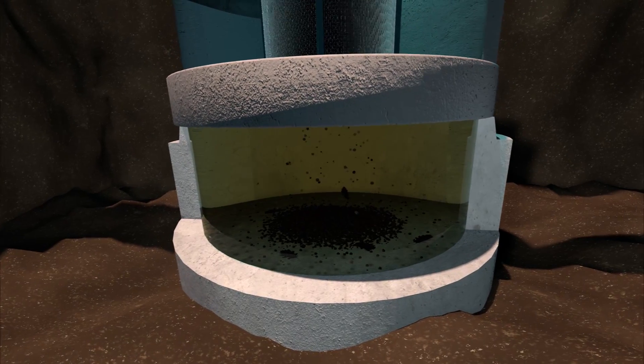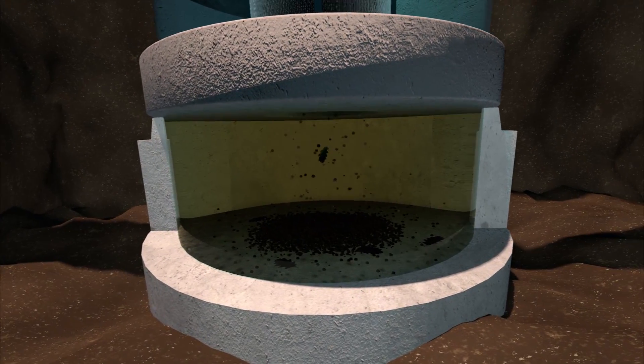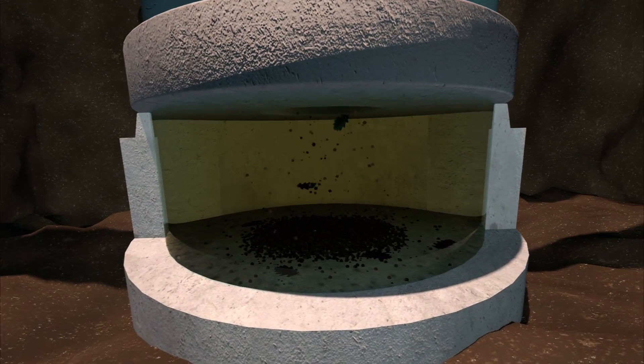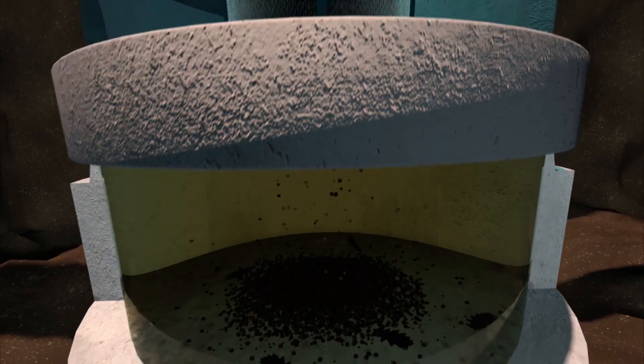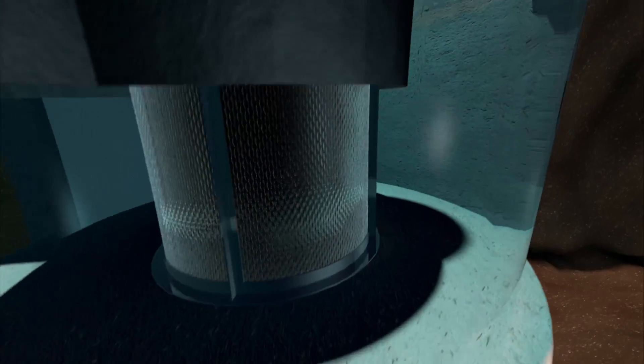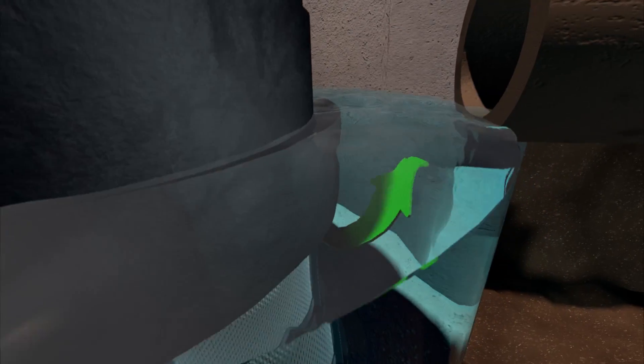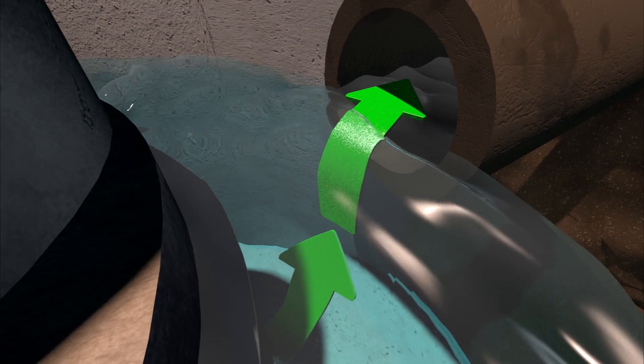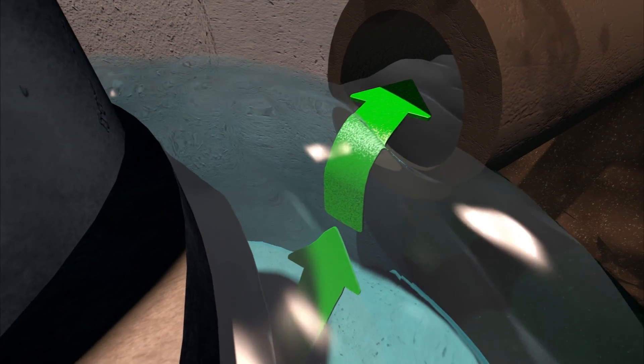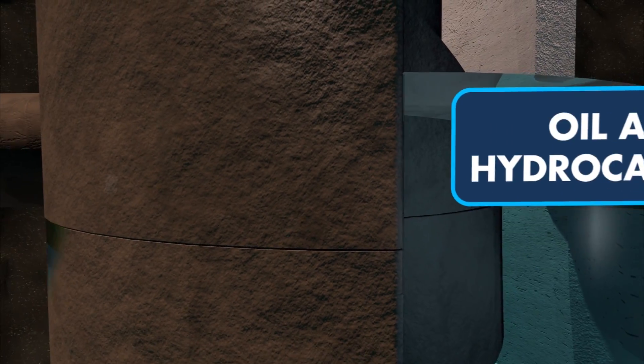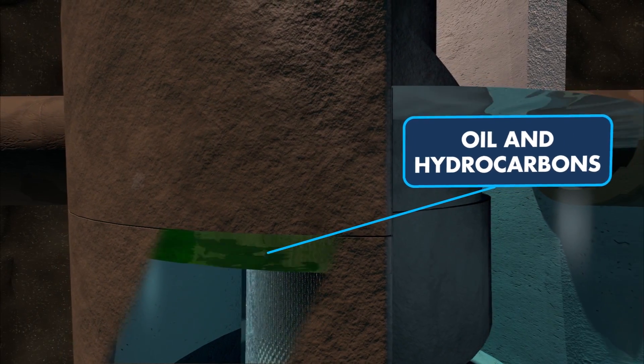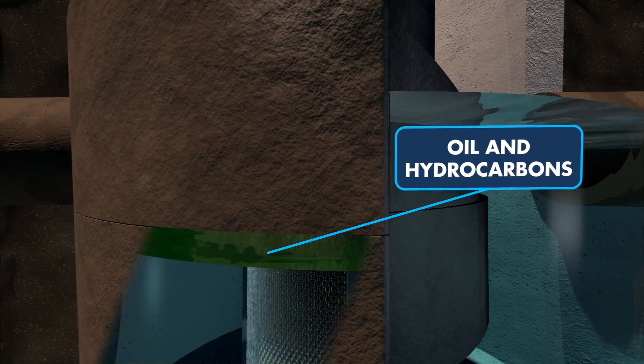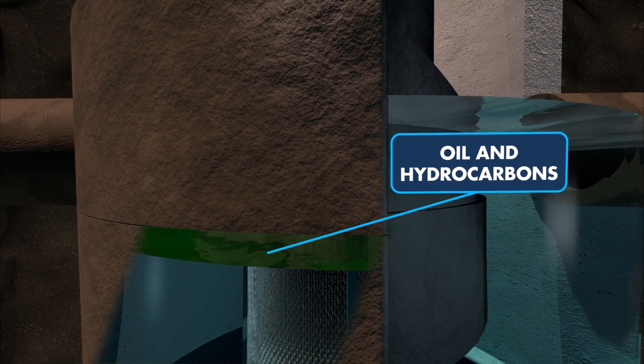Pollutants remain in these sections of the unit until they are removed during maintenance. Stormwater then moves under the hydrocarbon baffle, and the treated water exits the system. The baffle acts as a wall for hydrocarbon containment and prevents agitation of hydrocarbons when high flows spill over the diversion weir.